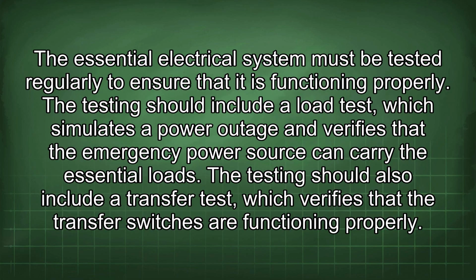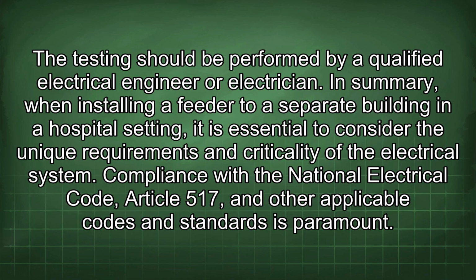The essential electrical system must be tested regularly to ensure that it is functioning properly. The testing should include a load test, which simulates a power outage and verifies that the emergency power source can carry the essential loads. The testing should also include a transfer test, which verifies that the transfer switches are functioning properly. The testing should be performed by a qualified electrical engineer or electrician.